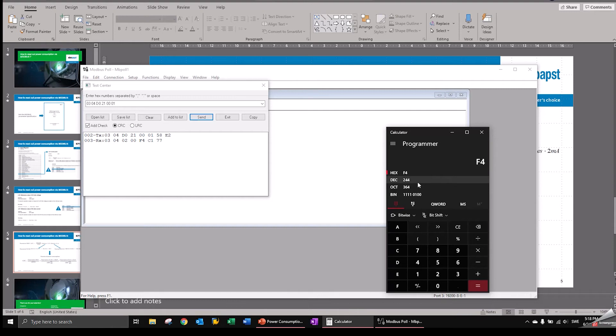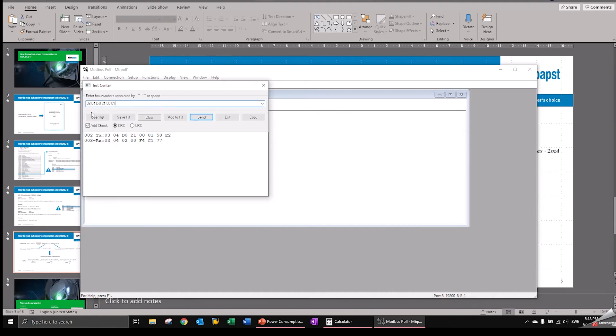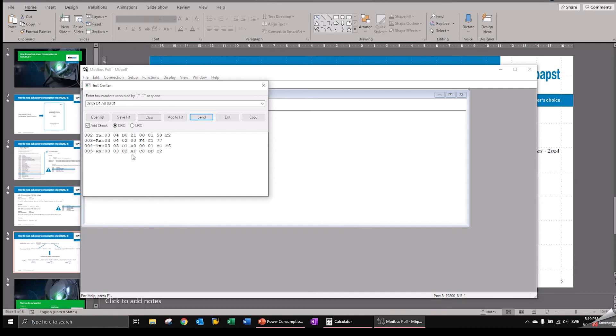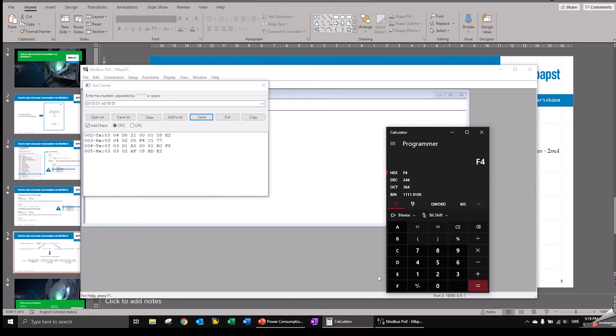So we note this down and now we want to read out the reference voltage. So we still talk to the fan with address three, but we also need a three here because we're reading out a holding register. The register is called D1A0. So let's put this in: D one, A zero, and we just want to read out that register. So the fan is responding. It's again responding with two bytes. So it's telling us now A F C eight. So let's put this here, A F C eight. That's 45,000 in decimal.